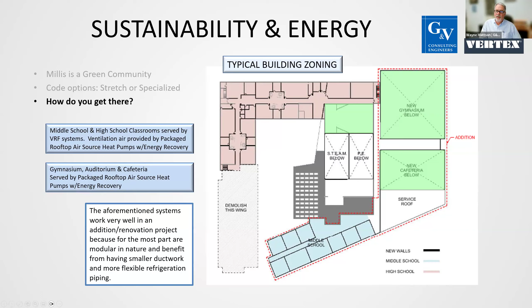Yeah. So AC light, we also call it a tempered air system. And the easiest way to think about that is think of your classrooms as being fully air conditioned up until June 20th, for example. So classrooms would not be fully air conditioned. What I mean by fully air conditioned, they don't have full air conditioning on the 95-degree day at the end of July or August. So if it was 91 degrees outside on July 30th, the inside of your classroom, if it's lightly loaded and based on high performing envelopes, the temperature inside your classroom is still going to be 75 to 78 degrees. However, it's going to be 50% relative humidity because the rooftop unit's going to handle the humidity regardless of the AC. So you're getting the benefit of a drier space, which gives you the opportunity to have a couple degrees warmer than you would. Now, your administration area, your library, and your student dining, that's going to be full air conditioning year round because you have people in the admin year round.